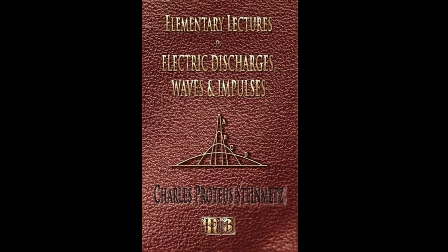Furthermore, the armature transient is not constant in its reaction on the field, but varies with the point of the wave at which the short circuit starts. Assume that the short circuit starts at that point of the wave where the permanent, or rather slowly transient, armature current should be 0. Then no armature transient exists, and the armature current is symmetrical from the beginning, and shows the slow transient of the field, as shown in Figure 23, where A is the field transient, the same as in Figure 22a, and B the armature current, decreasing from an initial value, which is m times the final value, on the field transient.